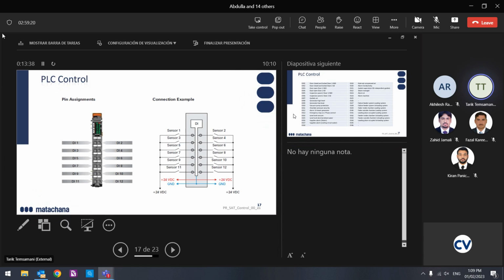You can go to the drawing and see digital input 6. What is digital input 6? Is this input? It's on. Okay, does it have to be on? Yes. So it's okay. Or maybe I have the door closed. Digital input 1, door closed. But it's not green. So I have a problem in the communication. I have the door physically closed, but not serially. The machine shows me that the door is open. Okay. Here you can check what is the problem exactly.